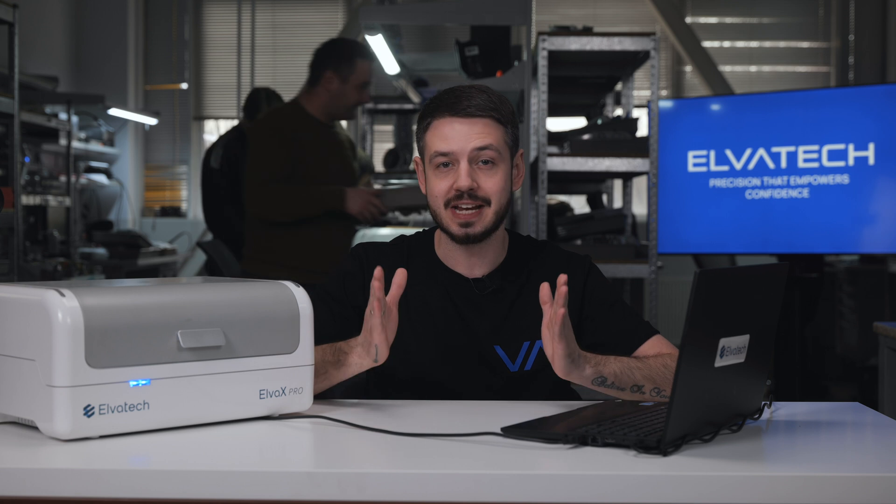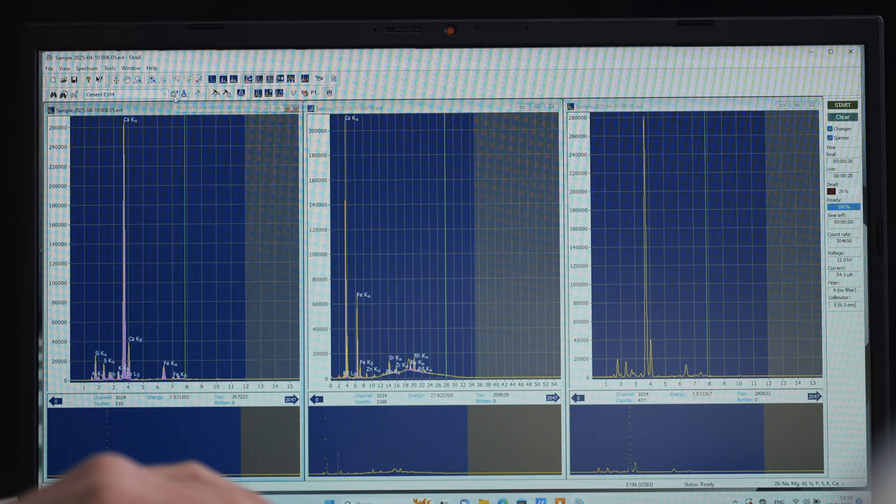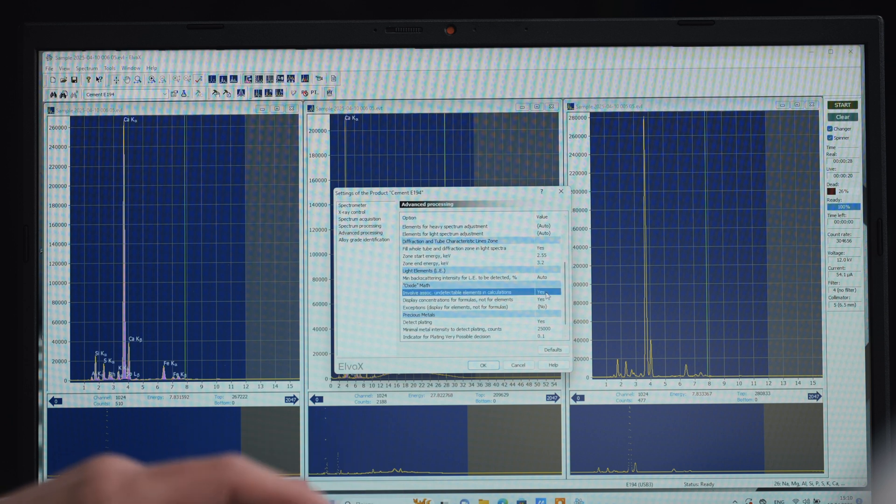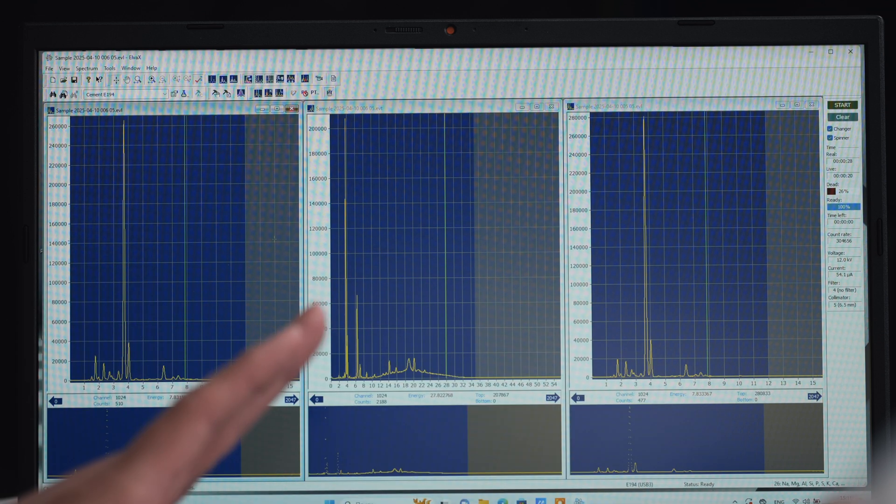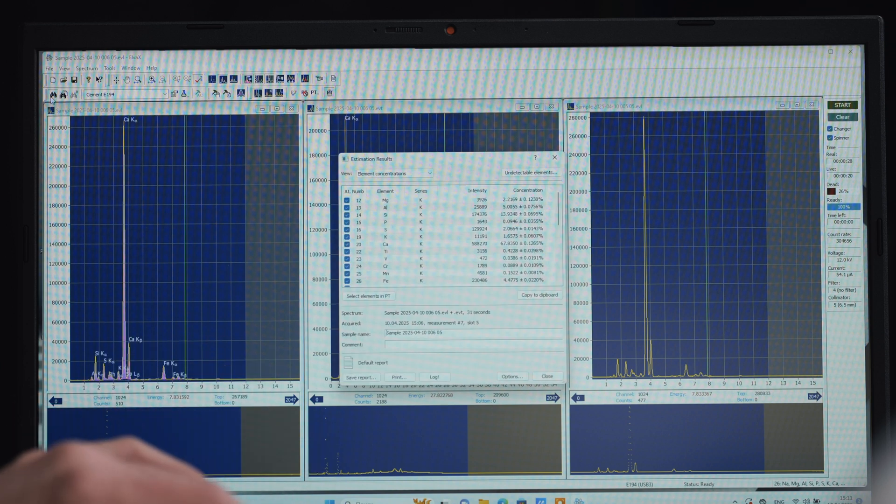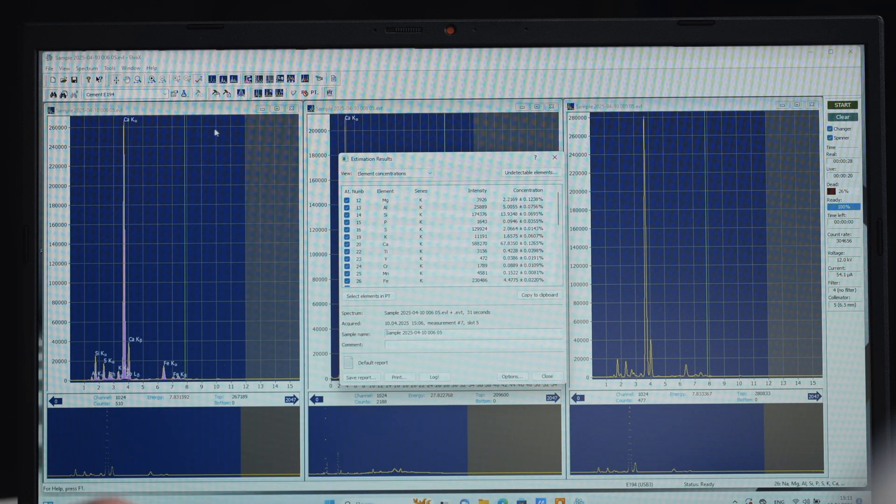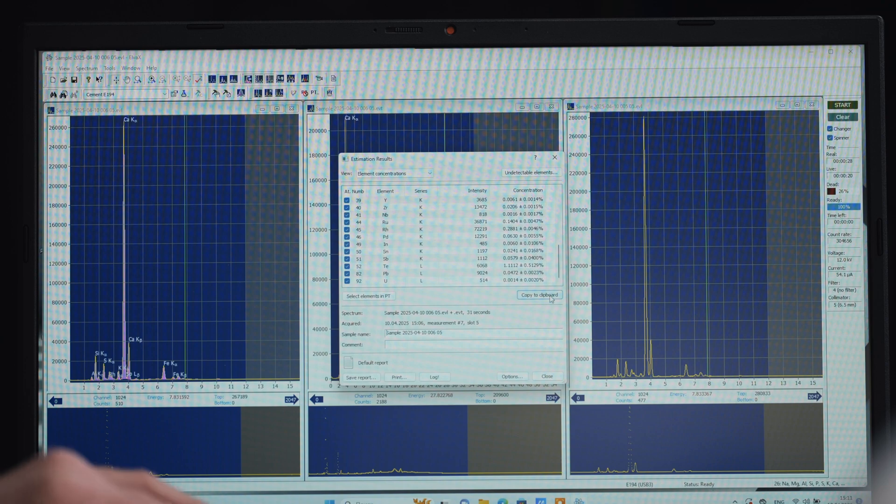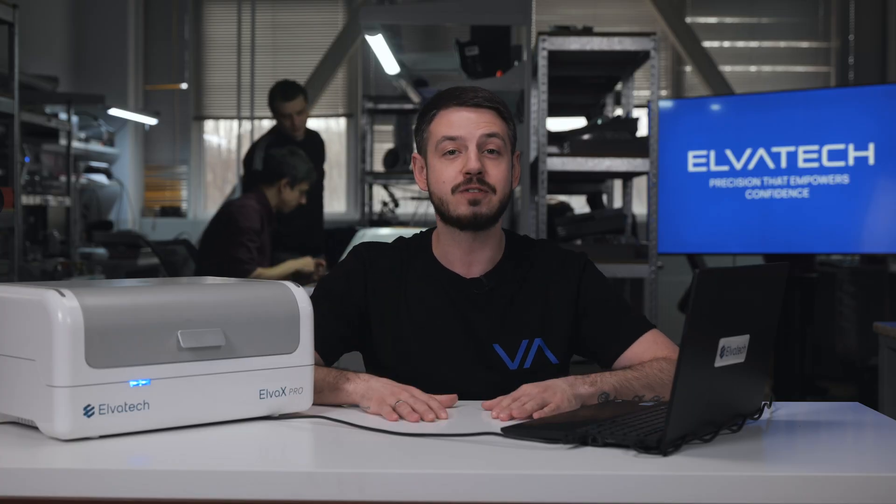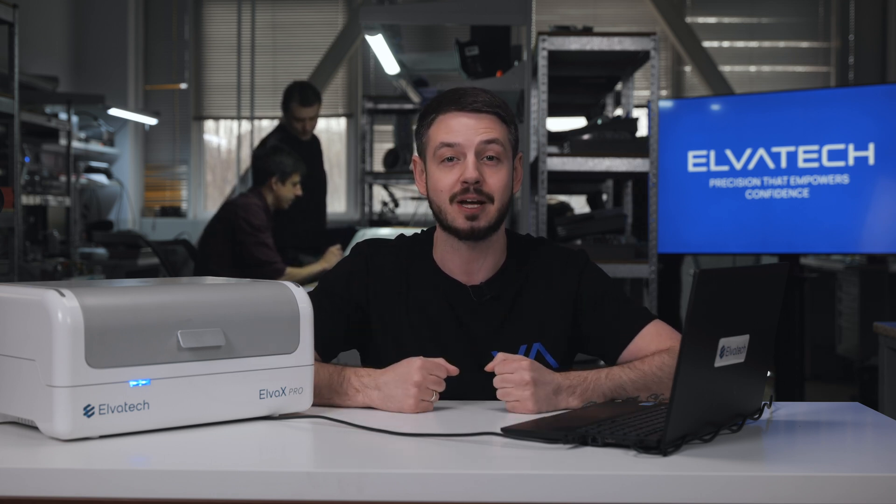That was about oxides. But if you need to have just the elements that are present in this sample, it's going to be very easy. Again, we go into this section called product parameters. On the advanced processing, where we have the section of oxide mass, you need to just unmark those two fields that we just marked previously. In the same way, you just click twice on this position and then press OK. Then, without any repeated measurement, we just go into the binoculars section here, where we have the estimate picture of our elements presented in this sample and also their concentrations. You can save this report. In such cases, you will have two reports of the same sample, but one will be in oxide form, another just the elemental composition.